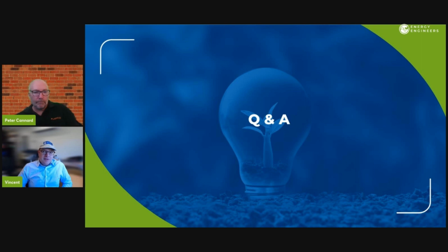Peter, a really good example of this also: I have a client that installed a couple of million dollars worth of laser cutting machines, and we asked them, well besides your power usage, what's your power factor, and what's the harmonics coming off the machine? Because these laser cutting machines are very high tech, very sensitive equipment, and he didn't know - in the procurement process, looking at those things was not something they considered.